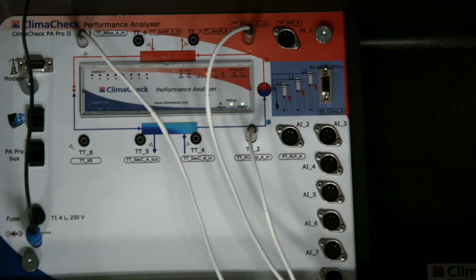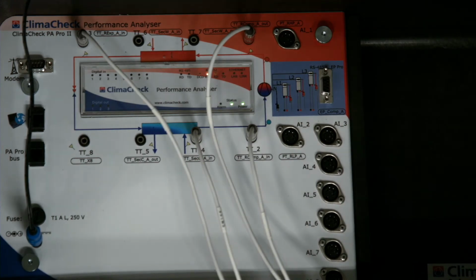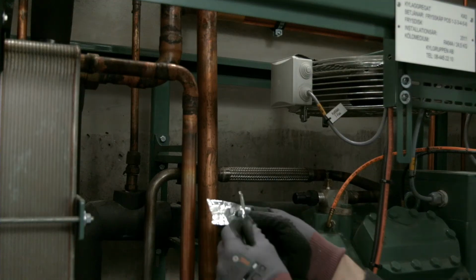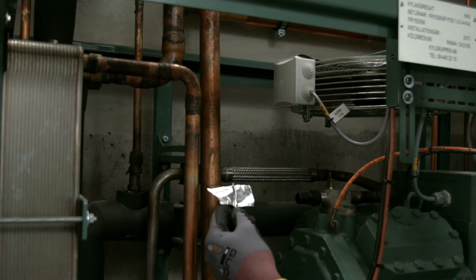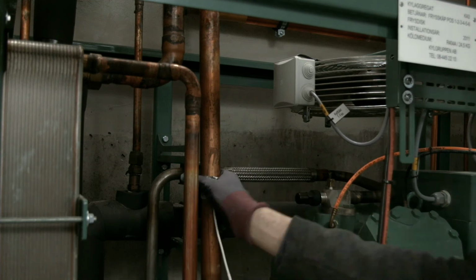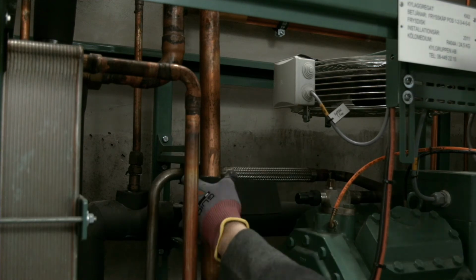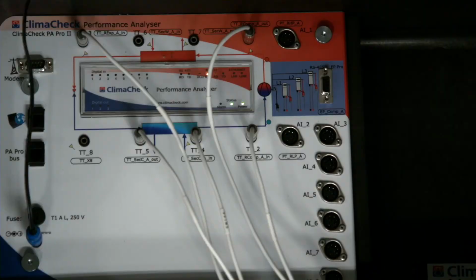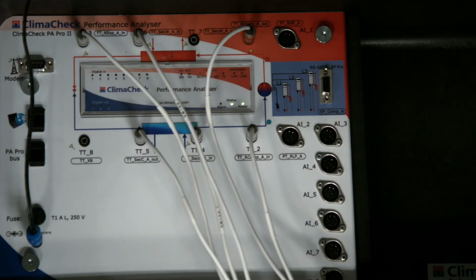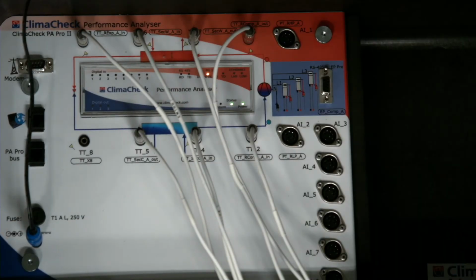Chill water in and out are connected, or evaporator air on and off. Secondary flow. The secondary flow for the condenser must also be connected. Remember that ClimaCheck does not need these values, but it's very, very good practice to connect them.